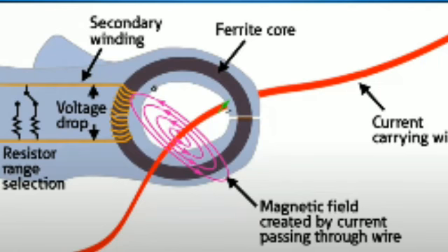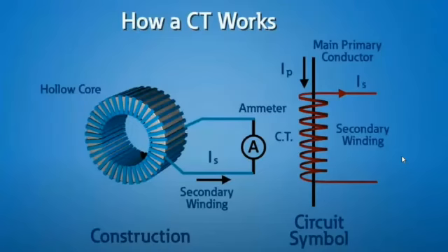can be determined. It is very important that the secondary of the current transformer should not be kept open. Either it should be shorted or must be connected in series with a low resistance coil such as a current coil or wattmeter coil or ammeter, like this.